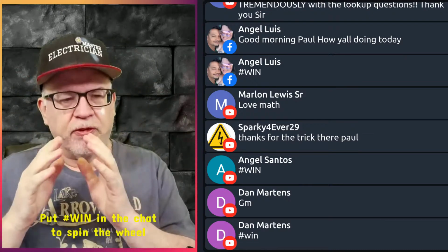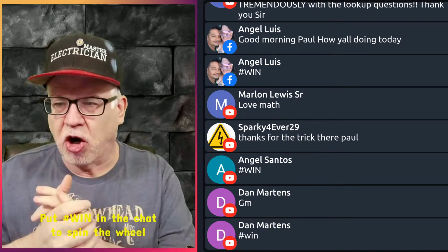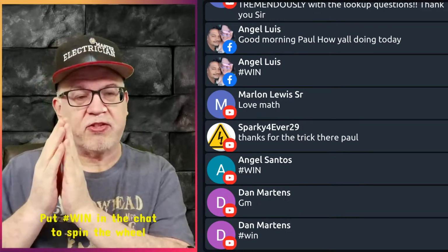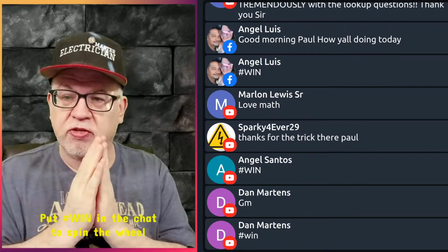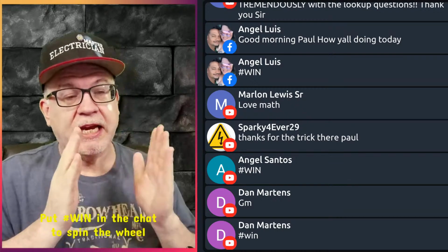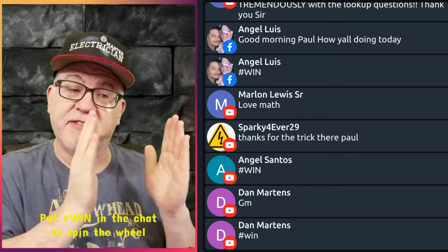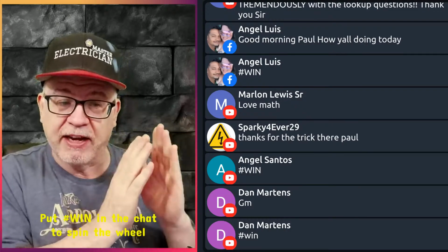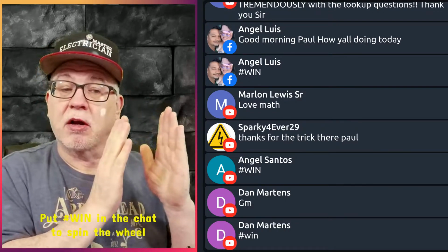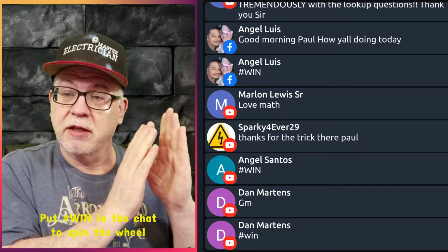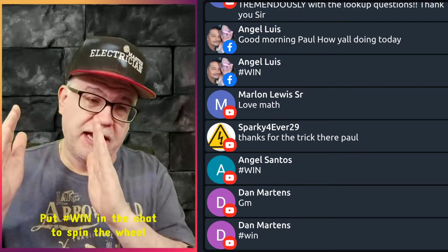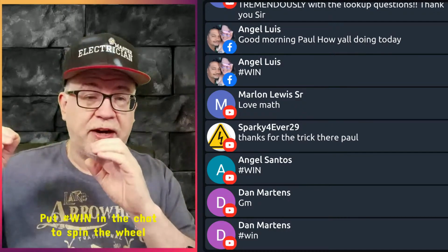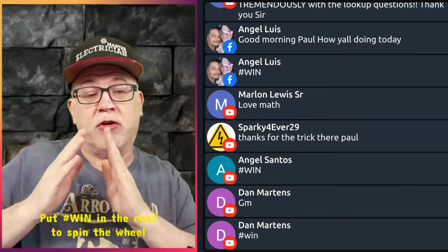So for the larger ones, that are 4/0 and larger, those will be done in a single layer. Those that are smaller than 4/0, you're going to have a certain area. They could be stacked, but they can't exceed the volume for that area. And that area is going to get smaller and smaller the more larger conductors you have. This makes sense, right? If the larger ones have to be on one layer, then that's going to take up a lot of the tray. That's going to make for a bigger tray.